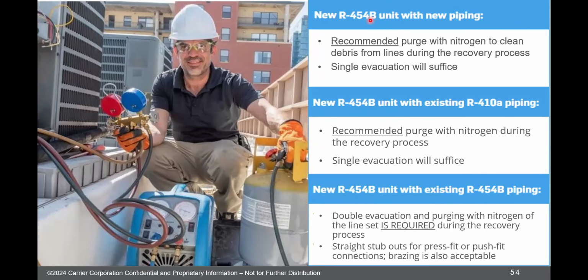The first one on top, R454B with brand new piping, so a brand new line set. They want you to purge and evacuate the line set. So you purge it with nitrogen to clean all the debris that could have got in the line, evacuate it, and then you're good to go, right? So on new piping, purge and evacuate once. If you want to do a double evac, you can do that. If you want to do a triple evac, you can do that. No one's going to complain that you did extra work, but single is all that's required.